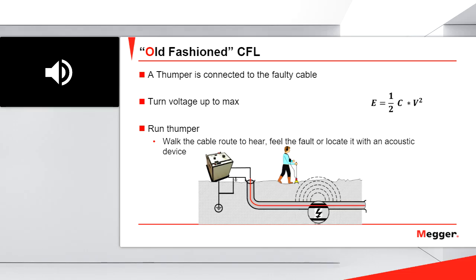And the reason we need to increase the voltage up to the maximum when we use this method is because of the equation that we are seeing on the right. In this method, we need to hear the fault, and we need to hear it very, very clearly. For that reason, we need a big bang, and if we need a big bang, we need a lot of energy. And if our thumper has a fixed capacitor, the only way to increase the energy, the only way to increase the bang, the loudness of the arc at the fault, is by increasing the voltage.